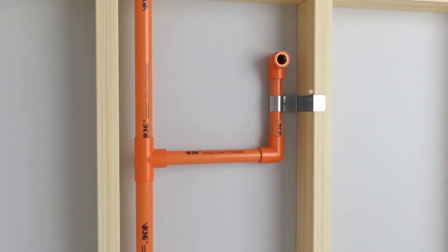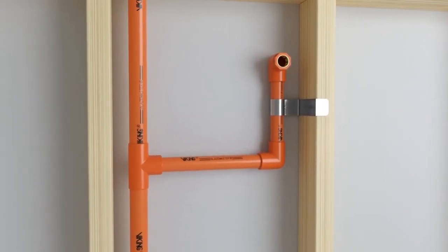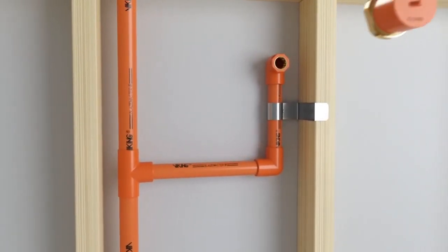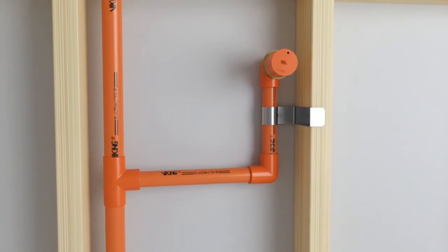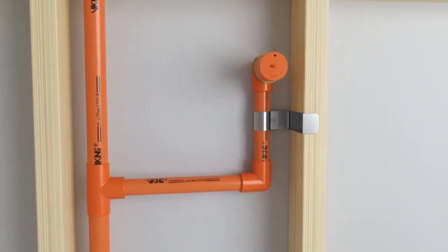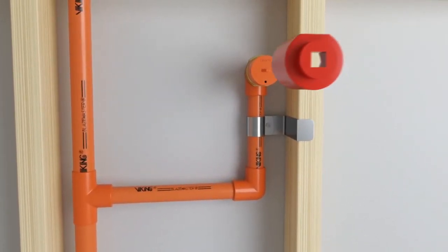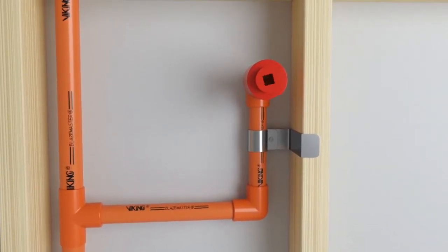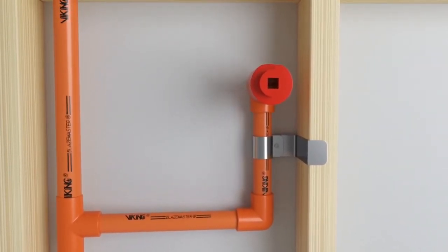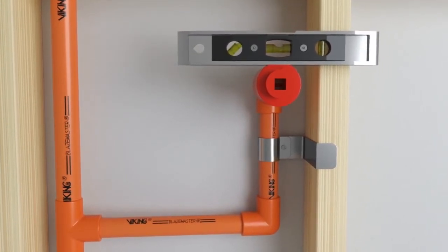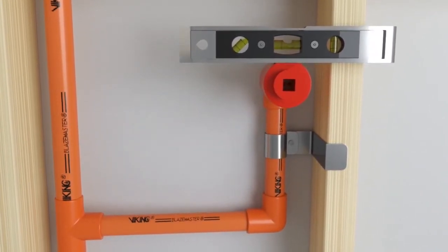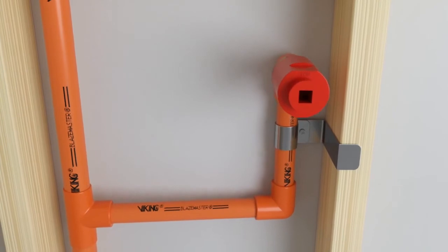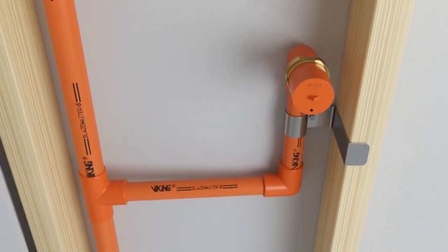So if you had 2x4 construction and you wanted to install residential in a 13R application, where you're looking at that 0.1 density, we also have an offering to fit in the 2x4 construction. So both the VK480 at a 4.0 K factor and the VK490 at a 5.8 K factor would allow you for that type of installation in that environment.